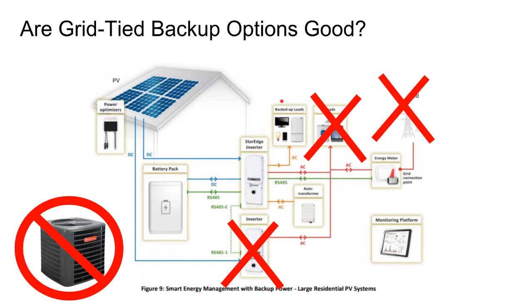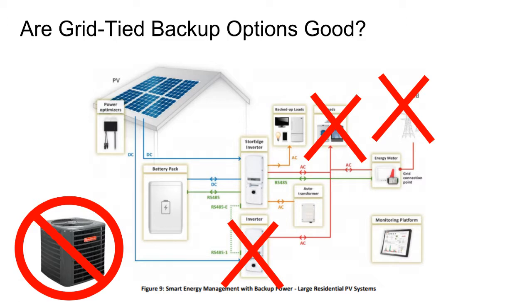In fact, if you take a SolarEdge battery inverter and a SolarEdge batteryless inverter and put them on the same service panel during a blackout, even though you're wiring a communication circuit between the two inverters, you're still not allowed by the manufacturer to turn that batteryless system on and power your whole service panel.